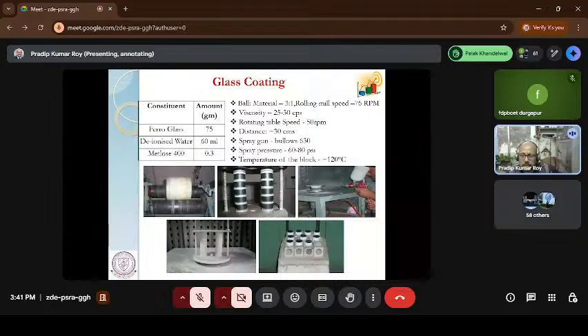So they mix the glass powder with a binder system. It is basically polymer Metolose 400, and they optimize the viscosity, which is very much required to coat the block around the varistor. Again, everything has to be optimized: what kind of pressure is required, what viscosity, what solid content, because we make a slurry. When I talk about slurry, there is a solid versus liquid ratio. Based on that, they optimize the slurry and coated it.